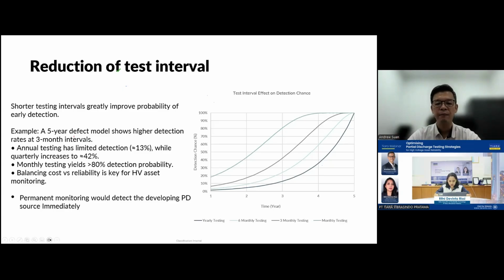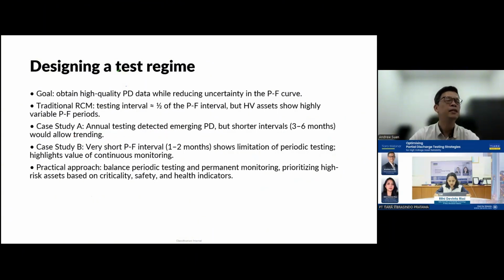Let's come to the next slide. You must know how to design a test regime. You must ask yourself, what's your goal? Is it to obtain high quality PD data while reducing the uncertainty of the point to failure curve? The traditional RCM testing interval is half of the P to F interval, but HV assets show highly variable P to F periods.